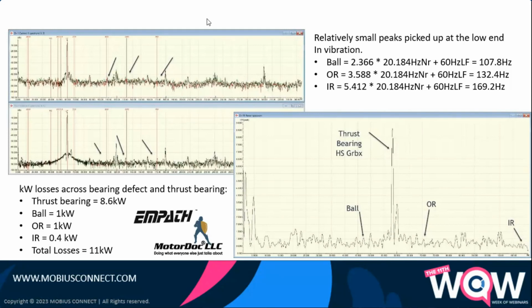We just have the one time, and a small peak. So if I see 3 to 5 dB above the noise floor, I know I have a defective bearing. So in this case, when we took a look at it, we found the thrust bearing had the highest load. They were concerned about the others.